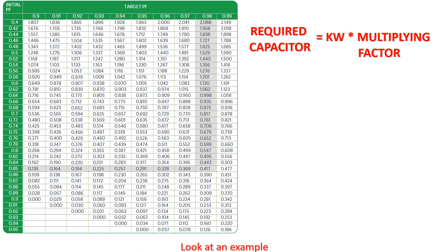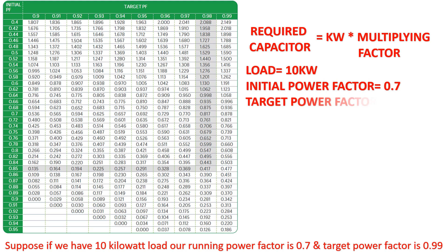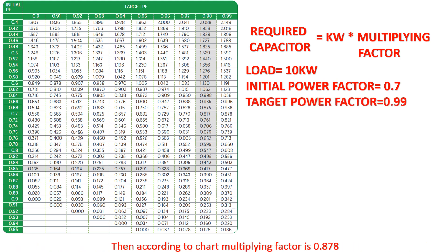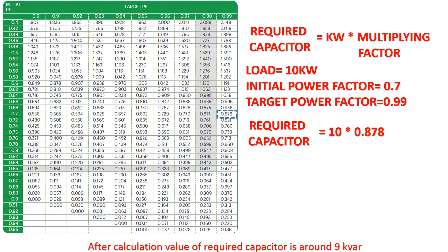Look at an example. Suppose we have a 10 kilowatt load, our running power factor is 0.7, and the target power factor is 0.99. According to the chart, the multiplying factor is 0.878. So the required capacitor is equal to 10 into 0.878. After calculation, the value of the required capacitor is around 9 kVAR.